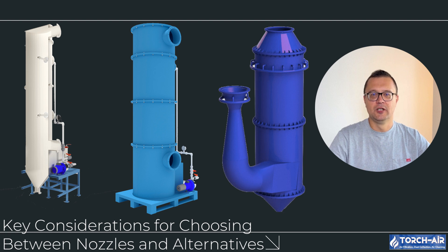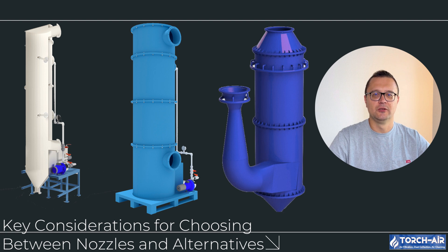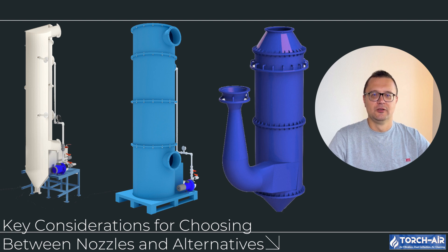Key considerations for choosing between nozzles and alternatives: selecting the right method depends on several factors. Type of contaminant: fine particulates and gases usually require nozzles to atomize the liquid and maximize gas-liquid interaction; for larger particulates or basic gas scrubbing, water overflows or trays might be more effective. Flow rate: high gas flow rates might benefit from simpler methods like overflows or liquid seals, while lower flow rates with complex contaminants often need nozzle systems for precision. Maintenance: nozzles can clog, especially when handling dirty liquids or particulates, so where maintenance needs to be minimized, trays or overflows may be better suited. Energy consumption: nozzles require pumps and pressure systems which increase energy costs, while water overflows and trays are less energy-intensive but may not provide the same scrubbing efficiency for finer contaminants.